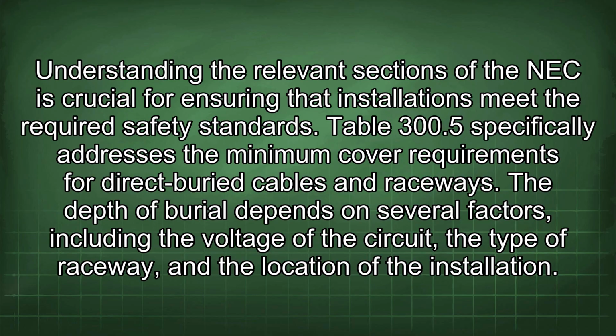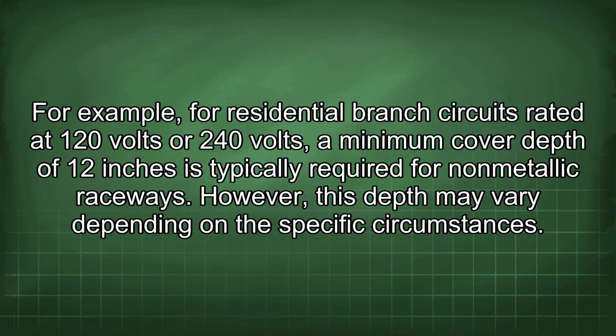Table 300.5 specifically addresses the minimum cover requirements for direct buried cables and raceways. The depth of burial depends on several factors, including the voltage of the circuit, the type of raceway, and the location of the installation. For example, for residential branch circuits rated at 120 volts or 240 volts, a minimum cover depth of 12 inches is typically required for non-metallic raceways. However, this depth may vary depending on the specific circumstances.